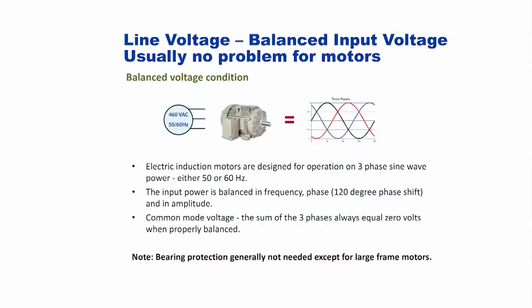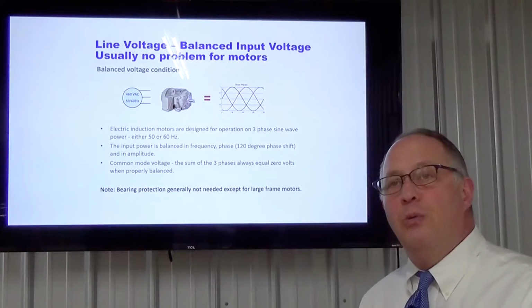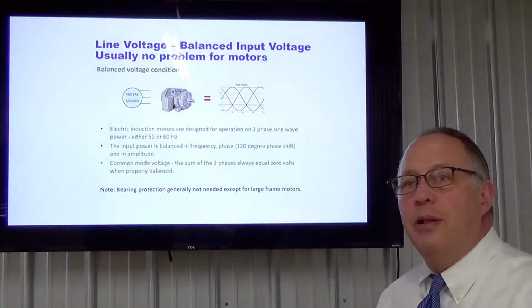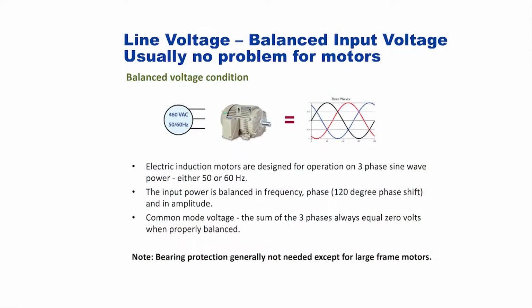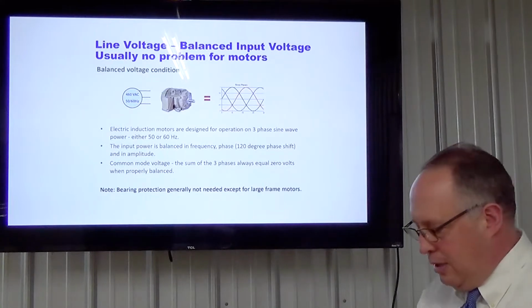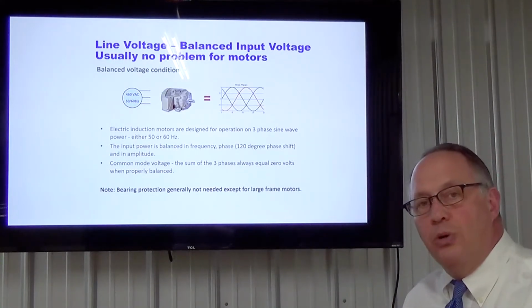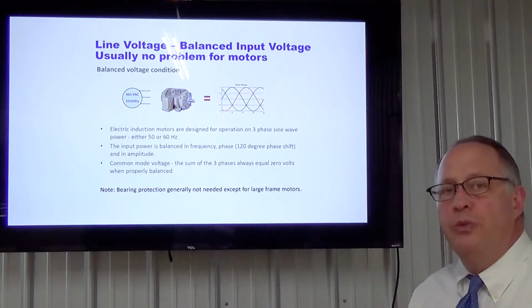What do those do to us? Well, let's talk about what it doesn't do. If we were to go just with a standard off-the-shelf motor and apply across the line, strictly line voltage, on balanced input, we usually have no problem with those motors. Typical 460 volt going in, we got 3-phase currents. They are essentially balanced. Electrical induction motors are designed for operation on 3-phase sine wave power, either 50 or 60 hertz. The input power is balanced in frequency, phase 120 degrees apart, in amplitude, and the common mode voltage, the sum of all 3 phases, usually equals about 0 when properly balanced. Note, bearing protection is generally not needed except on large frame motors. So straight across the line, you're just running the motor at 460 volts, 208 volt, 240 volt, 3-phase, you don't have a problem.